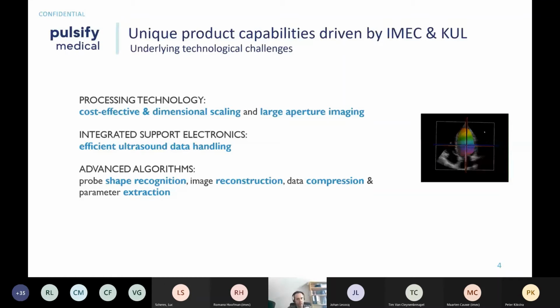You have several key requirements if you want to monitor the heart with such an ultrasound patch. Your patch needs to cover a relatively large area, to cover a big enough part of your chest to view the heart. It needs to be flexible, and if it's wearable, it had better also be cost effective. Such a sensor is not out there yet in the market, which is why we're custom developing it together with our partners at imec. They are real drivers to develop this new technology.